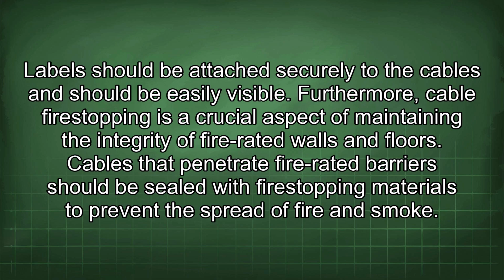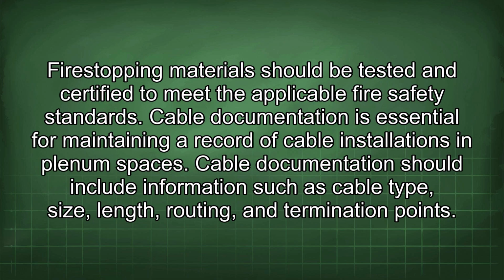Furthermore, cable fire stopping is a crucial aspect of maintaining the integrity of fire-rated walls and floors. Cables that penetrate fire-rated barriers should be sealed with fire-stopping materials to prevent the spread of fire and smoke. Fire-stopping material should be tested and certified to meet the applicable fire safety standards. Cable documentation is essential for maintaining a record of cable installations in plenum spaces. Cable documentation should include information such as cable type, size, length, routing, and termination points.